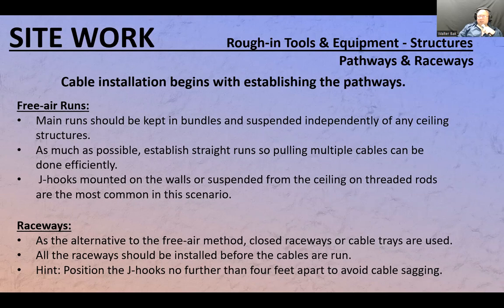The other thing is, when, God forbid, there is a fire, then you're going to have some fire crews moving in and dealing with what they have to deal with. And sometimes what they have to do is they have to get those kind of hooks on a stick, right? And just grab some of the ceiling structure and pull it down, so they can get to whatever they can. It's part of their job, right? So if there's some other things strapped to that ceiling structure, it makes things more difficult, and plus it's an uncontrollable environment when they are dealing with a fire situation. So it makes their job more dangerous. All right. So that's why we should install wires independently.